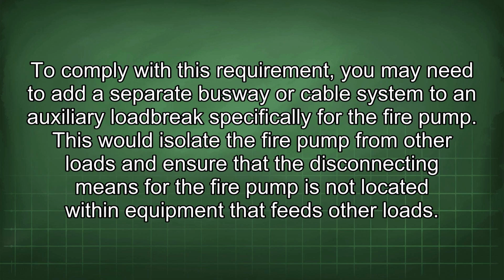To comply with this requirement, you may need to add a separate busway or cable system to an auxiliary load break specifically for the fire pump. This would isolate the fire pump from other loads and ensure that the disconnecting means for the fire pump is not located within equipment that feeds other loads.